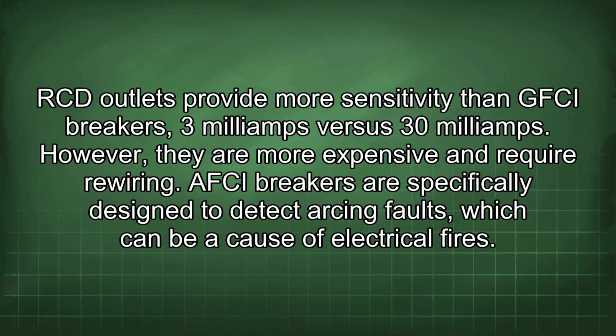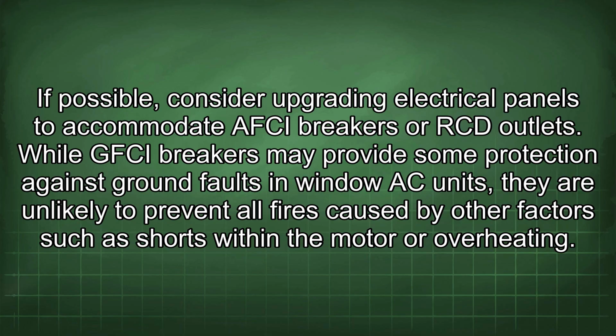RCD outlets provide more sensitivity than GFCI breakers, 3 mA versus 30 mA. However, they are more expensive and require rewiring. AFCI breakers are specifically designed to detect arcing faults, which can be a cause of electrical fires. If possible, consider upgrading electrical panels to accommodate AFCI breakers or RCD outlets.